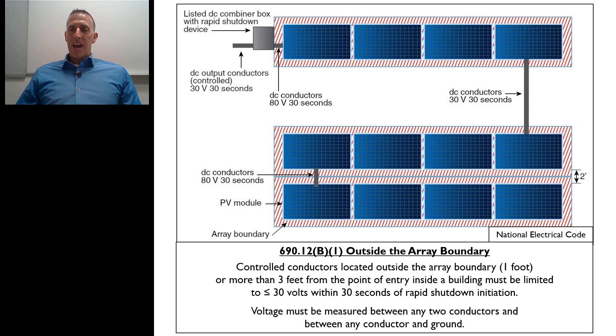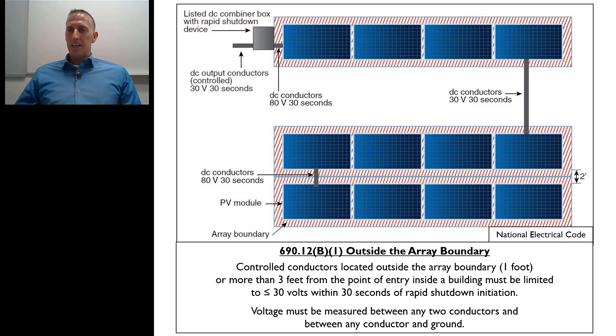Keep in mind: anything outside that array boundary — that one-foot boundary — or more than three feet inside the point of entry into the building, all of those conductors, when the rapid shutdown is initiated, must drop from whatever voltage they are down to 30 volts or less within 30 seconds. Similar to the 2014 code, voltage must be measured between any two conductors and ground. So the highest voltage between any of the conductors or any conductor and ground must be less than or equal to 30 volts within 30 seconds — every conductor has to meet that requirement. The maximum is 30 volts.